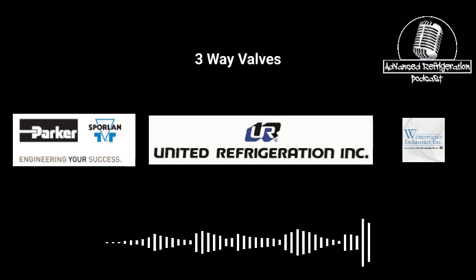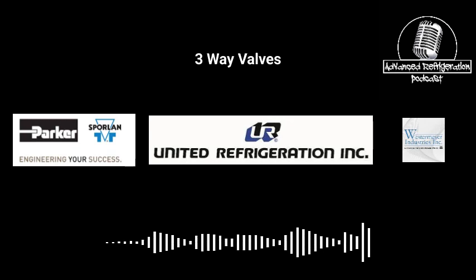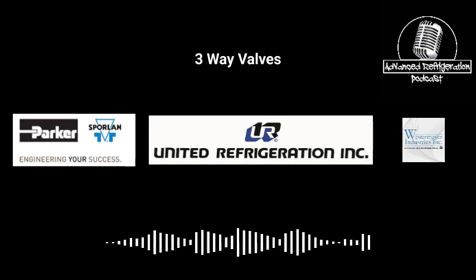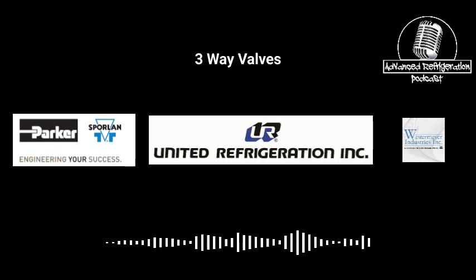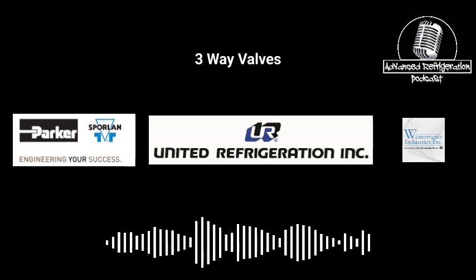The other valve that I was thinking about is the electronic load shedding valve that they use for, what store is that? It's a gas station. I think Quick Trip. They utilize a three-way valve in case the suction is maintained on the medium temp. If there's barely any compressors running, they can basically shift the load over to the low temp and just use it like that. Yeah, it'd still be a standard three-way valve or like a stepper, but it would be a different application. But yeah, along the same lines.